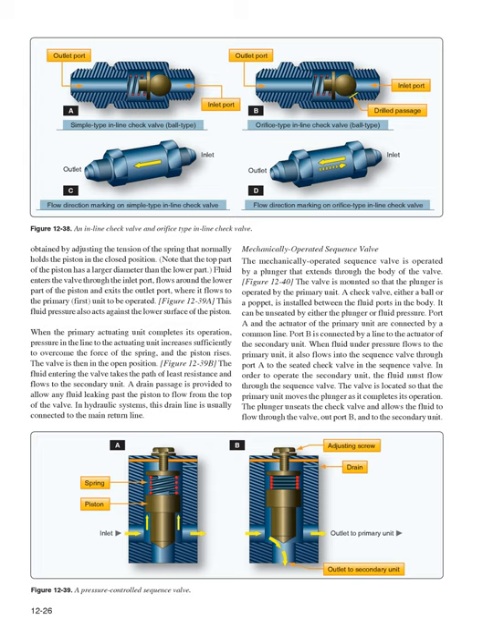When the primary actuating unit completes its operation, pressure in the line to the actuating unit increases sufficiently to overcome the force of the spring, and the piston rises. The valve is then in the open position. Figure 12-39b, the fluid entering the valve takes the path of least resistance and flows to the secondary unit. A drain passage is provided to allow any fluid leaking past the piston to flow from the top of the valve. In hydraulic systems, this drain line is usually connected to the main return line.